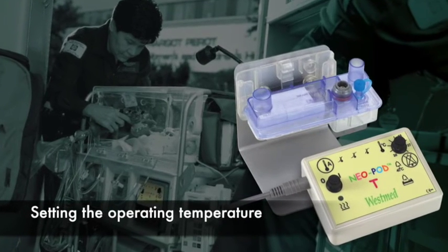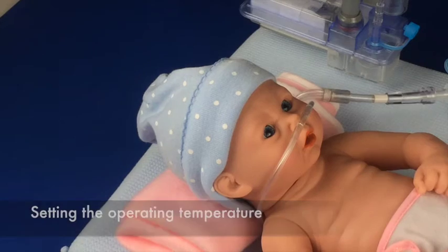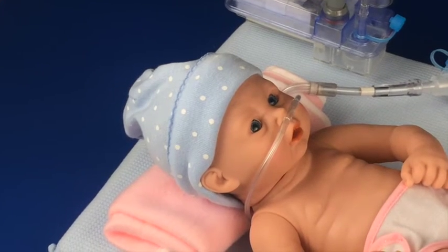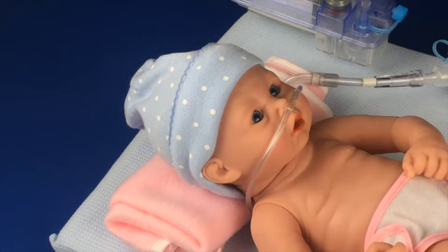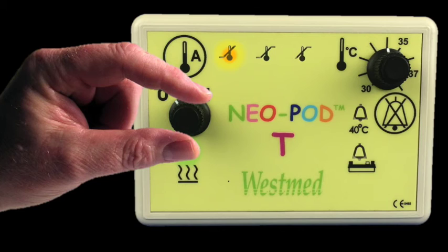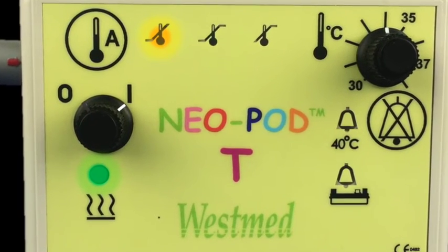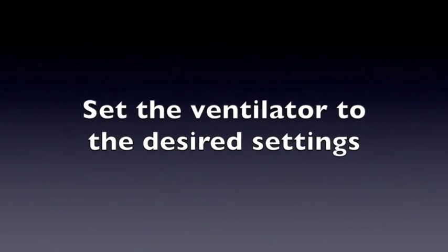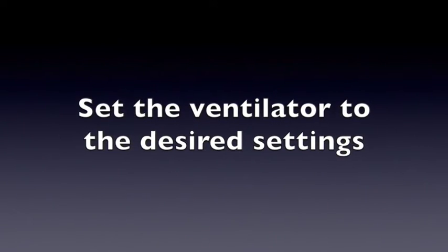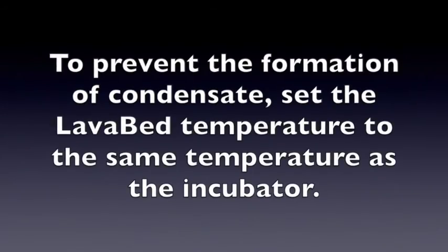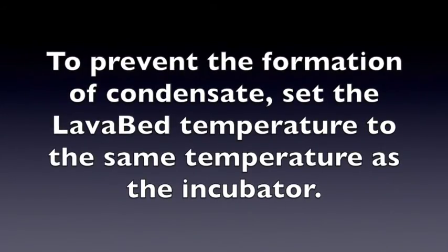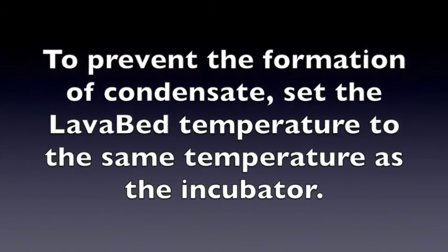Setting the operating temperature on the Neopod controller. After the setup is complete and the LavaBed cartridge is in place inside the incubator, turn the on-off switch on the controller to the on position. The LED light will show green for the on position. Set the vent flow to the desired level during warm-up. To prevent the formation of condensate, set the LavaBed temperature to the same temperature as the incubator.